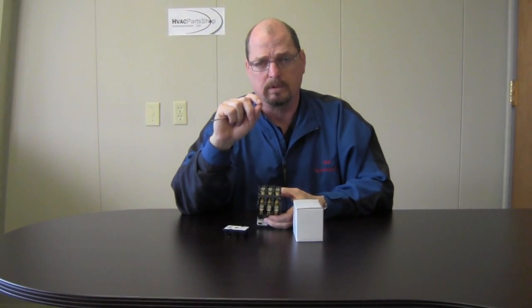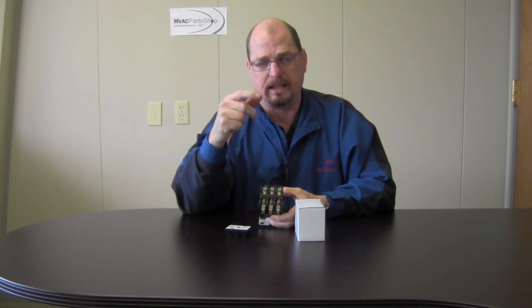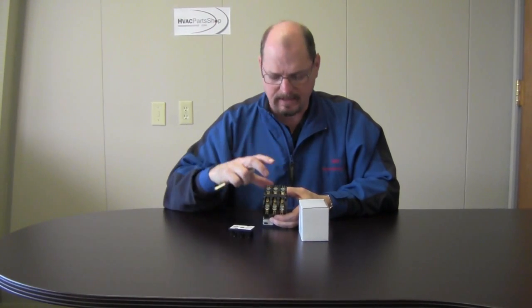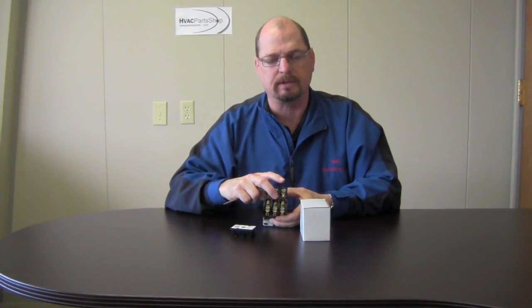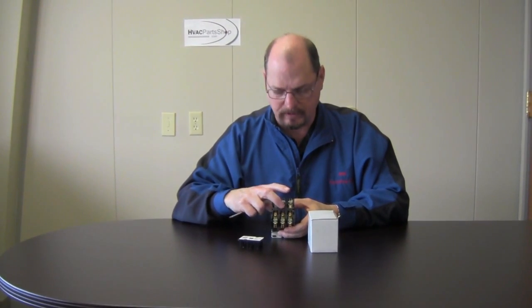Once we have that arcing then our points will start to pit. Once that happens then we can't make good contact on it, then we end up with high amp draws and that's how you burn out motors and stuff.